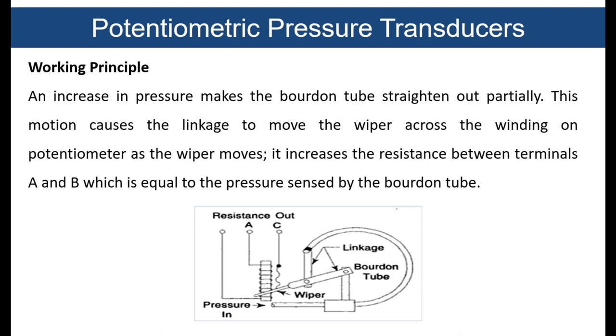Okay, now the working principle of this potentiometric pressure transducer. An increase in pressure makes the Bourdon tube straighten out partially. This motion causes the linkage to move the wiper across the winding on the potentiometer. As the wiper moves, it increases the resistance between terminals A and B, which corresponds to the pressure sensed by the Bourdon tube.